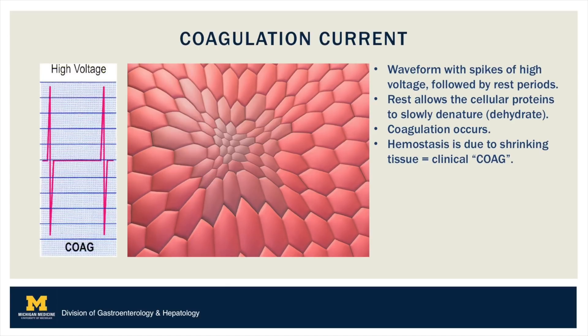A coagulation current is pulsed high voltage, often higher than the voltage of the cutting current but with intervening rest periods. This latency between pulsed episodes allows for dehydration of cellular proteins resulting in shrinking of tissue. This shrinking of tissue results in hemostasis via desiccation.